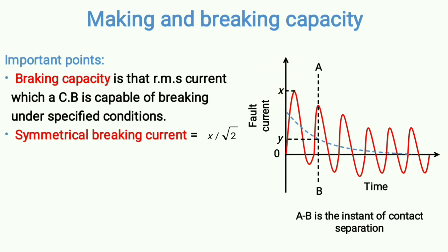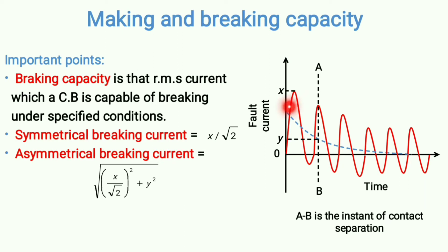In the presence of the decaying component, the fault current becomes asymmetrical. In the case of asymmetrical breaking current, we consider individual RMS values and the overall RMS value becomes √((X/√2)² + Y²), where Y is the value of the decaying transient component at the instant of contact separation.